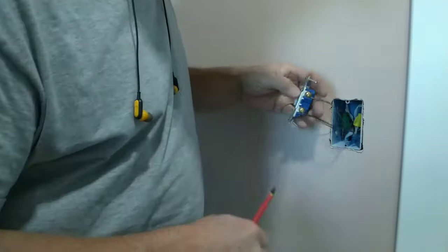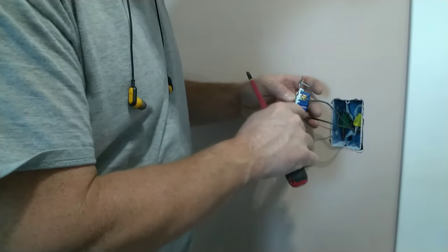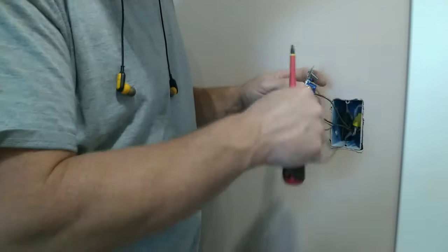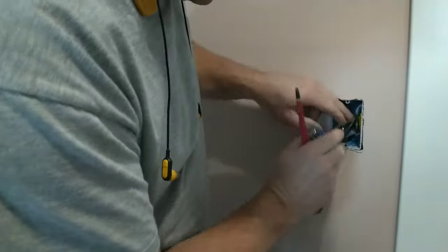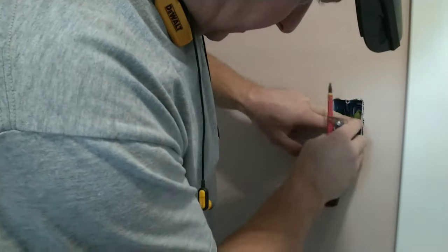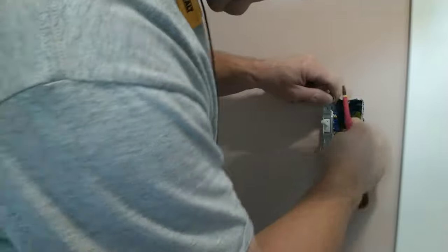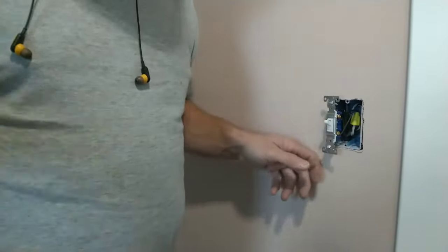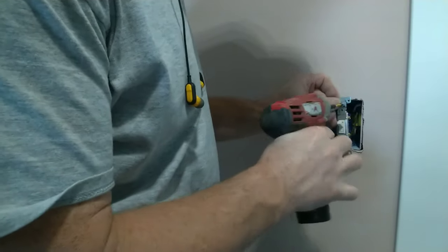Onto the light itself. Always turn in a clockwise fashion, and always make sure you hook the wire on so that when you're tightening it, the wire gets tighter and it doesn't spin off. Take your wires and coil your wires in the box so that you are not kinking them. No kinks. Radiuses are better than tight bends and kinks.